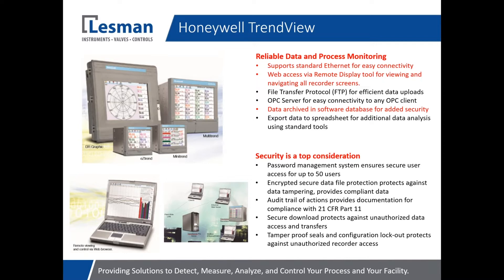Security is a really big consideration for Honeywell at this point. Their most recent firmware release for these recorders requires that the recorder have a security certificate that Honeywell issues in order to communicate over the Ethernet connection. I've spent some time in the past two weeks since the firmware came out explaining to people why it worked yesterday and now after the firmware change it doesn't. You get them set up with a security certificate — they email Honeywell, get it back a couple hours later, install it, and it's up and running. These things have worked out very well for remote access either through the web, FTP, or even through an OPC server.